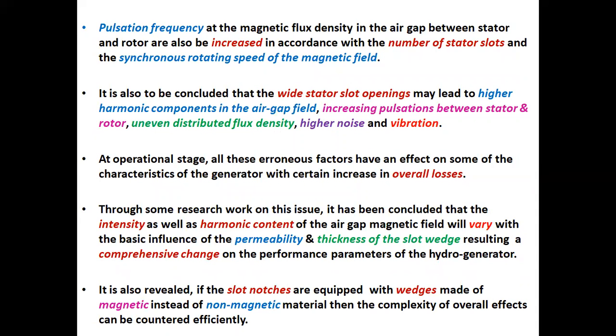Pulsation frequency of the magnetic flux density in the air gap between stator and rotor is also increased in accordance with the number of stator slots and the synchronous rotating speed of the magnetic field. It is also to be concluded that the wide stator slot openings may lead to higher harmonic components in the air gap field, increasing pulsation between stator and rotor, uneven distributed flux density, higher noise, and vibration.